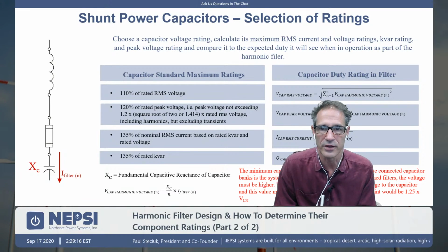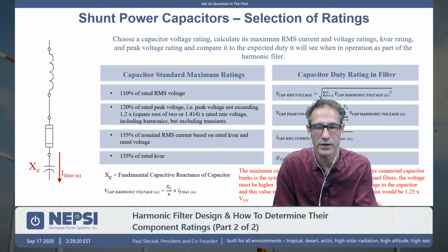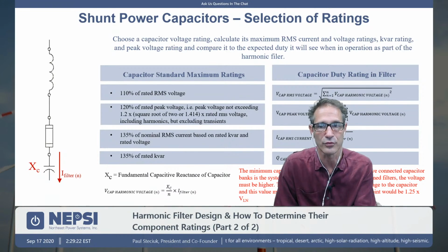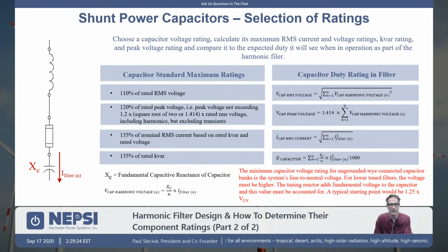Another thing to look at is the RMS harmonic current. We're just taking the sum of the squares of the harmonic current flow into the capacitor, and we're making sure that we're at that 1.35 per unit level. We want to make sure that we're always below that 1.35 per unit level for the capacitor. And typically that's not a difficult item to meet. Same with rated kVAR. We're calculating rated kVAR.